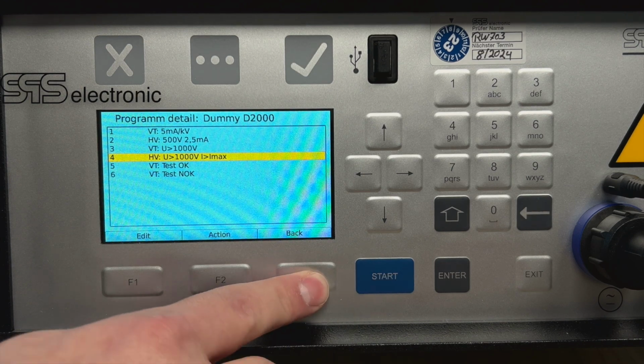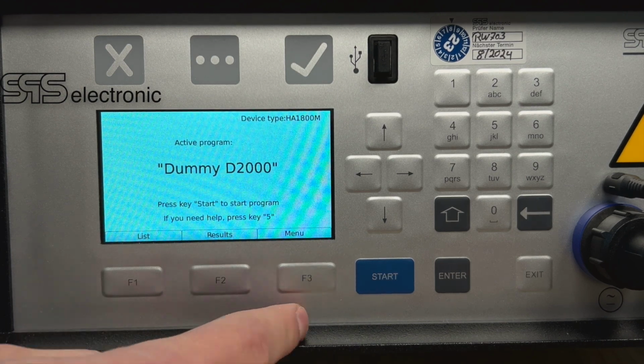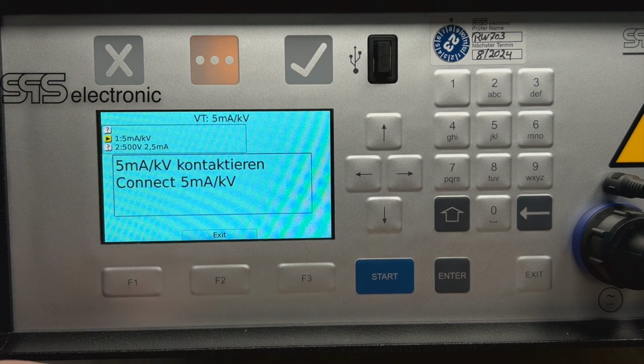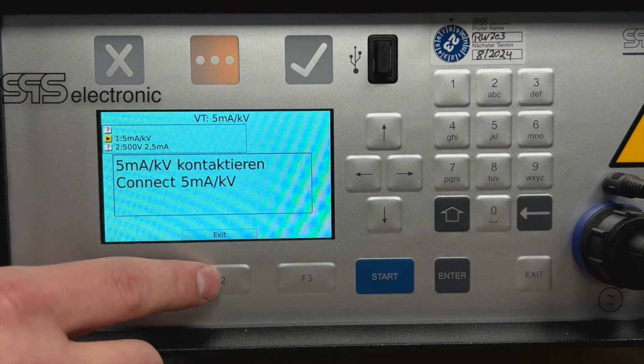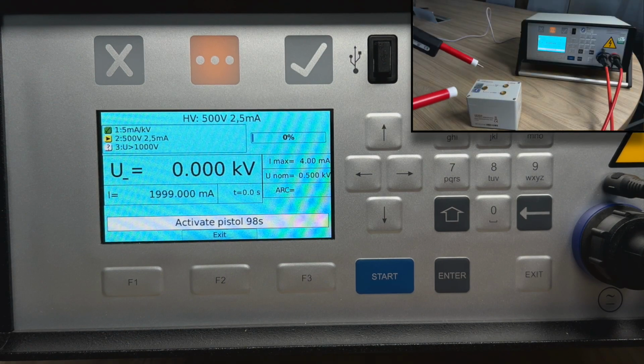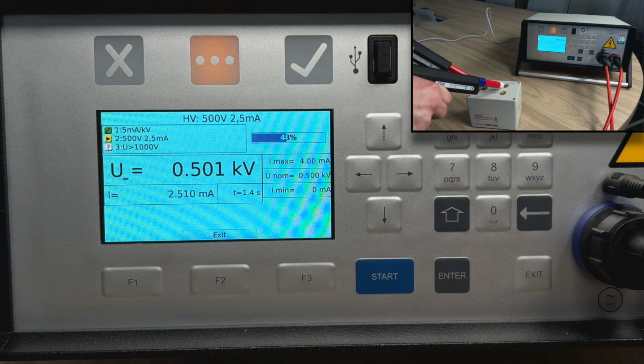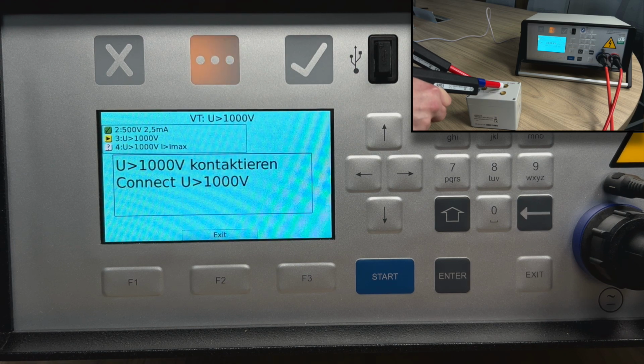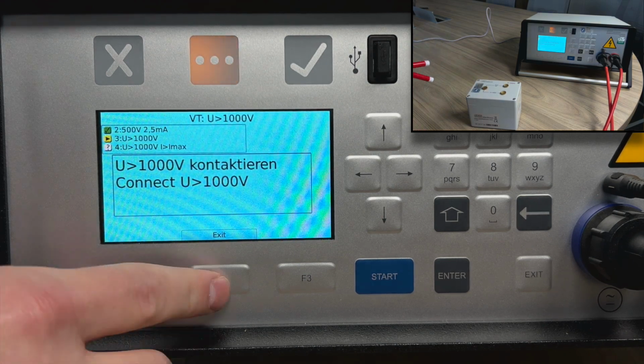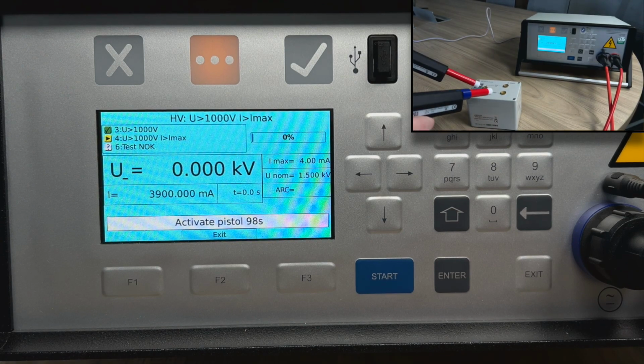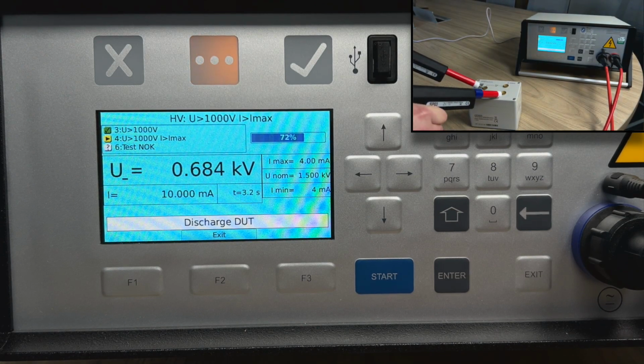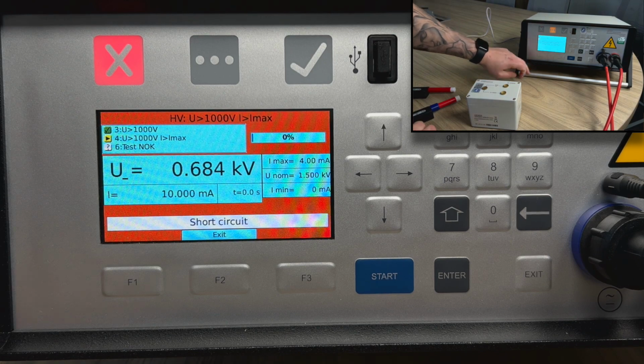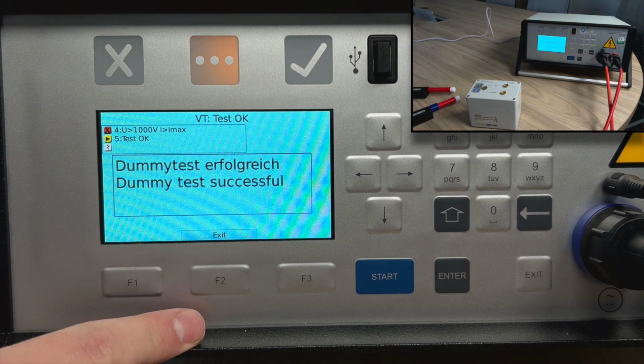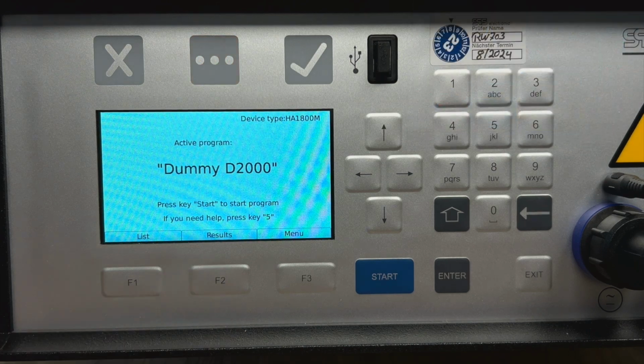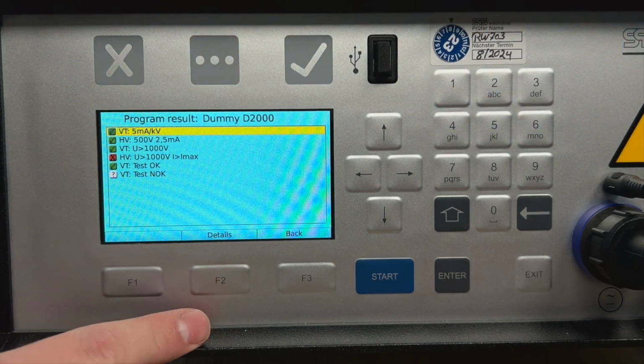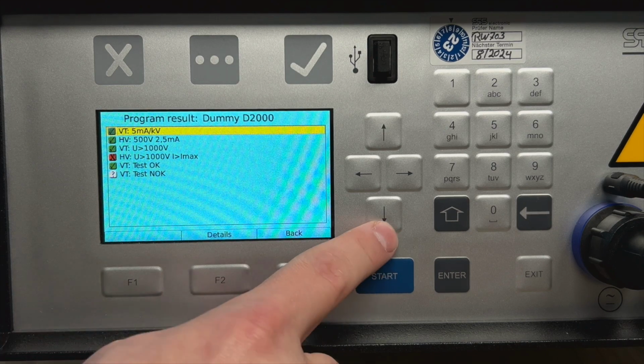From here we will go to main menu and start the test program. The first step will be visual text to inform us which pins we should connect. We will take our high voltage pistols and connect the pins. As you can see, 500 volts, 2.5 mA. The next step is also a visual step to inform us where to connect, and here near 1 kV we will get the short circuit, which means the test is complete. Then we can take a look at the results, and save them on the USB or internal memory.